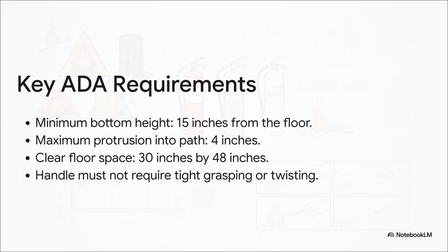But wait, the ADA has more to say. To make sure it's not a hazard itself, an extinguisher can't stick out more than 4 inches into a hallway. You also have to design for a clear 30 by 48-inch floor space in front of it for access. And look at this detail, even the handle is specified. It can't require tight grasping or twisting. Yep, these are all totally fair game for an exam question.